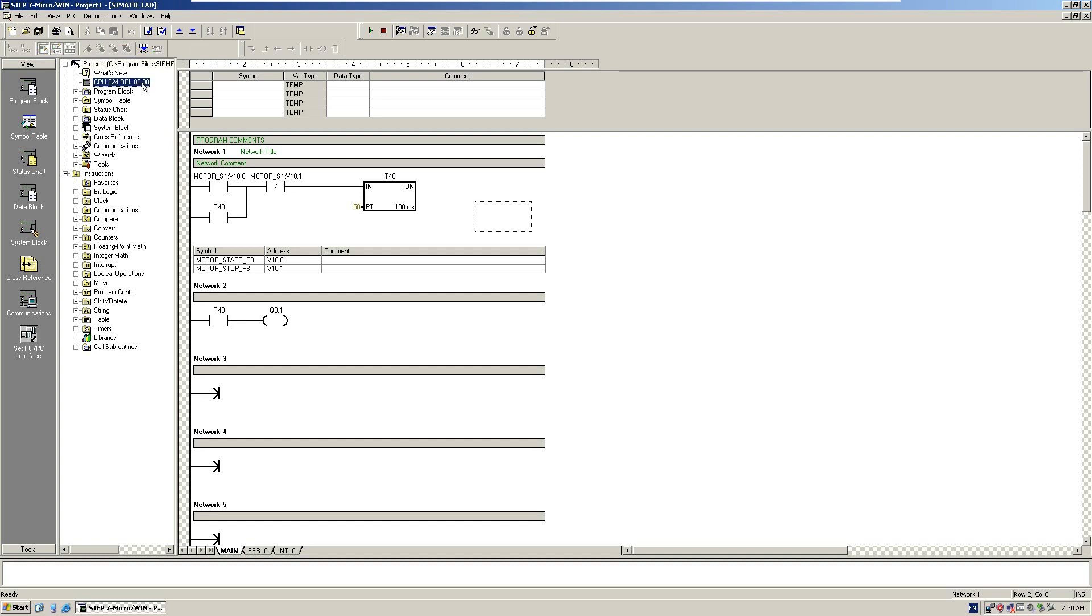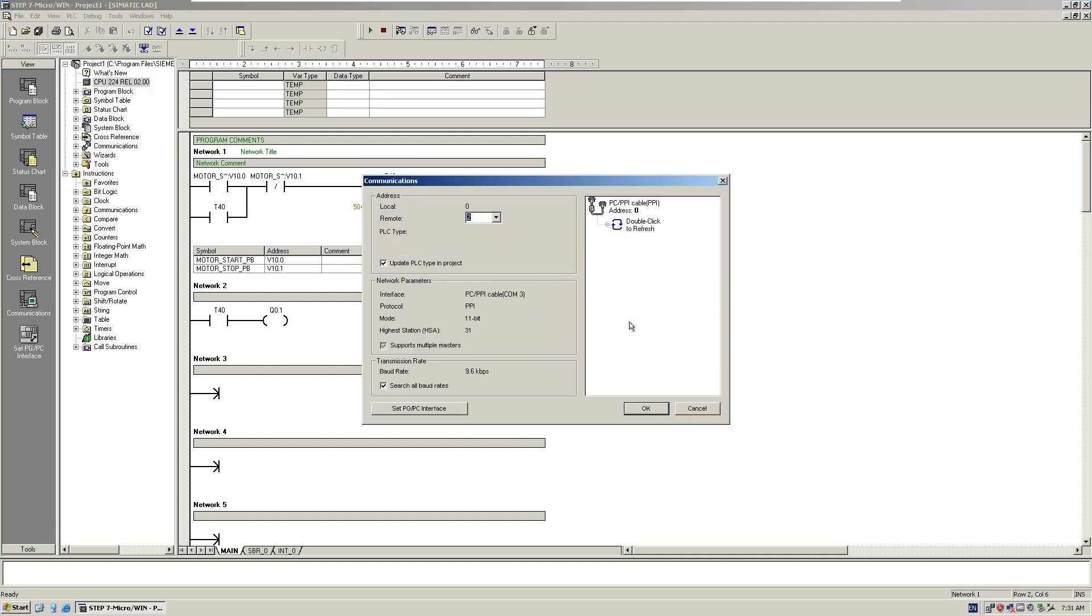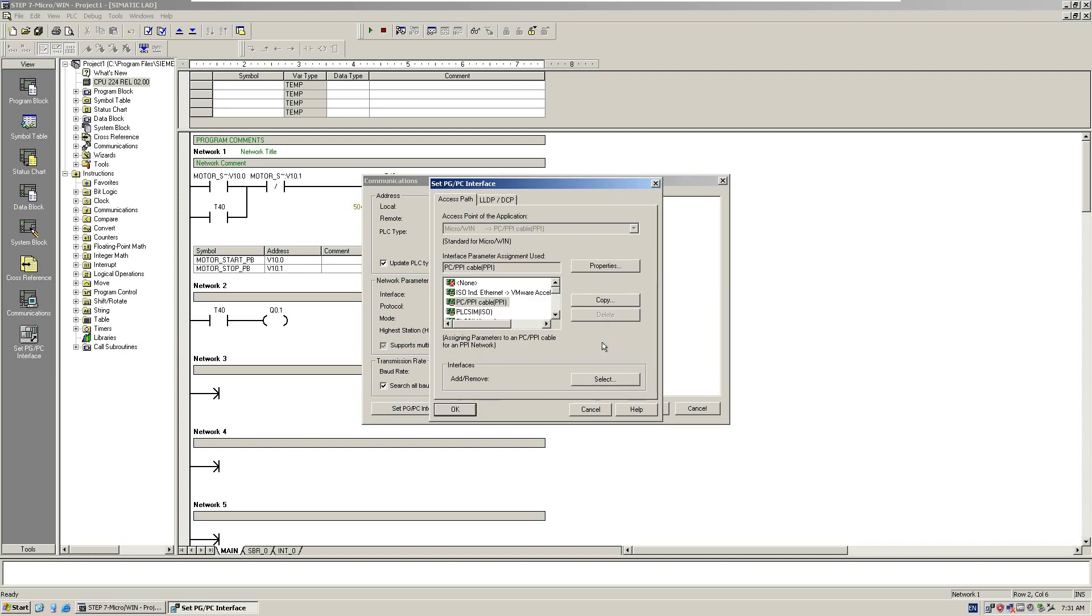Double-click this icon, the CPU icon here. Click the communication, go to Set PG/PC Interface. From here, we see this software is MicroWin. That is an access point in the Set PG/PC interface. The physical channel we will use is the PC-PPI cable with PPI protocol. We select this and go to properties.